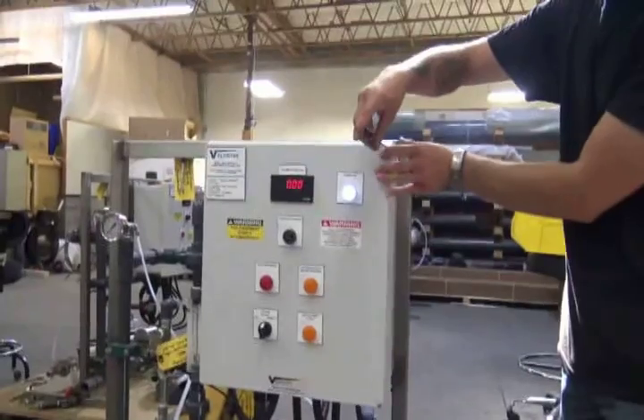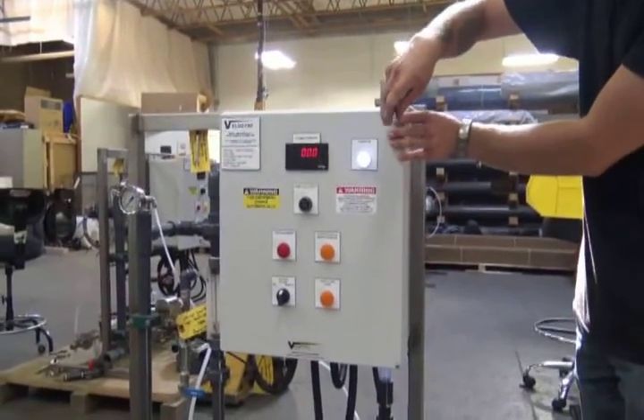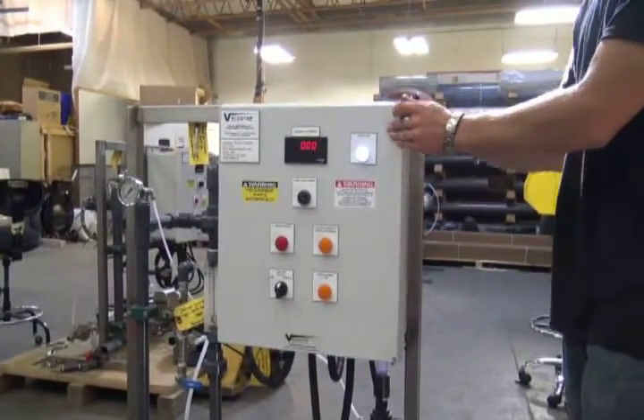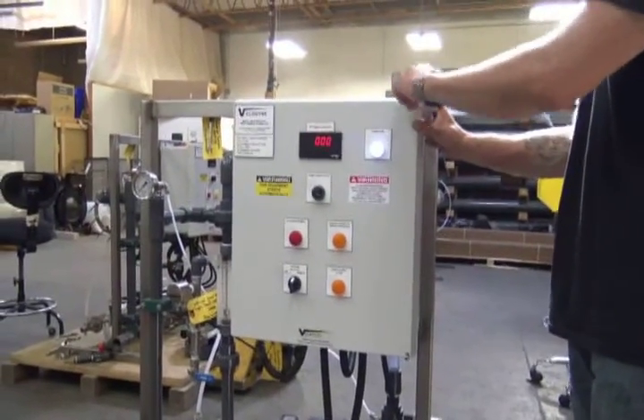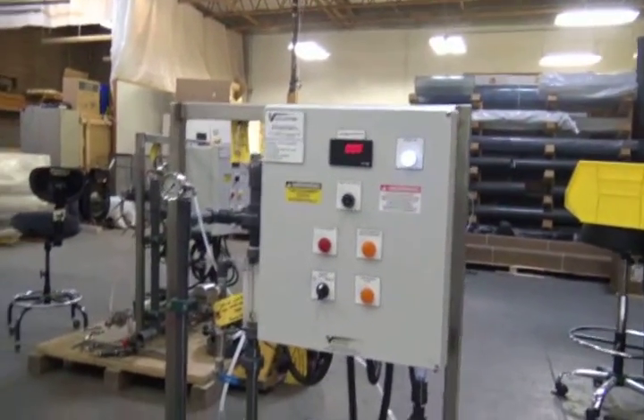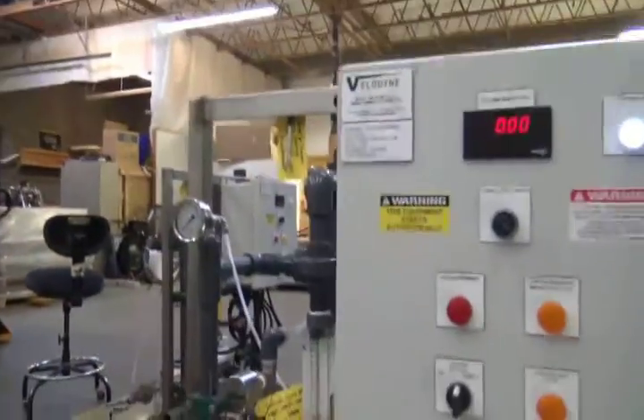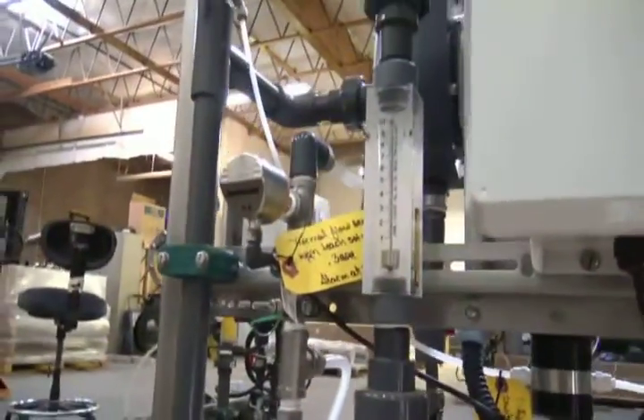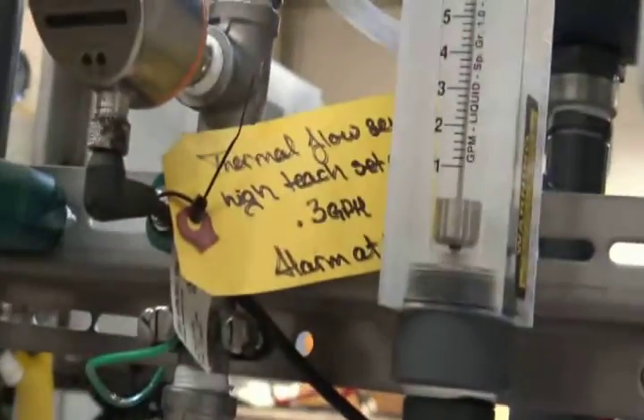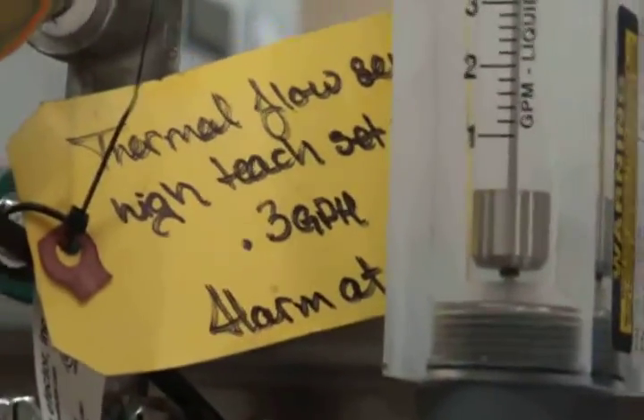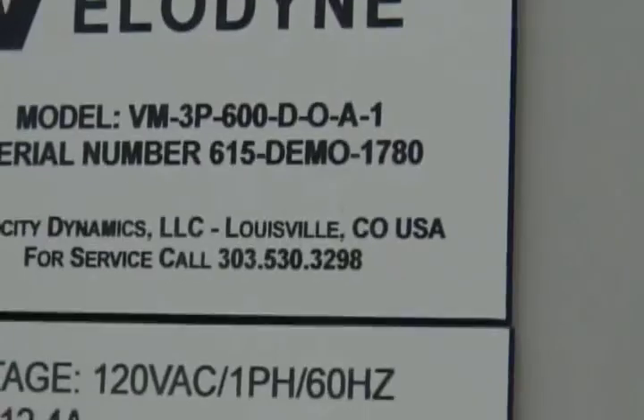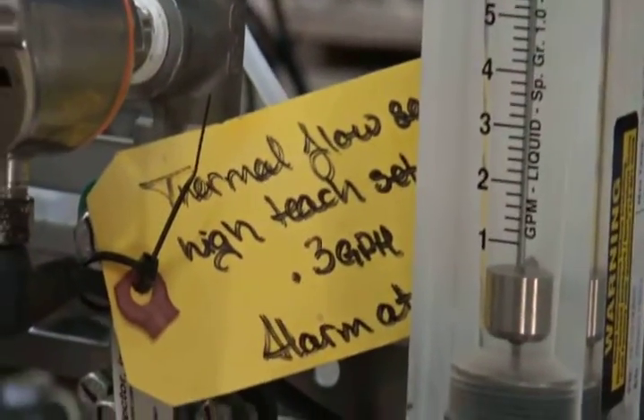Now we've got our signal wire disconnected, and it won't alarm the system while you're running it, because you're going to need to run it above and below that alarm set point that you're going to be setting. From the factory, we set these up with a 10 turn down for a high teach and then a 20 turn down for the alarm output. So this system here is a 3 gallon per hour progressive cavity pump, so we set it at 0.3 gallons per hour for the high teach.